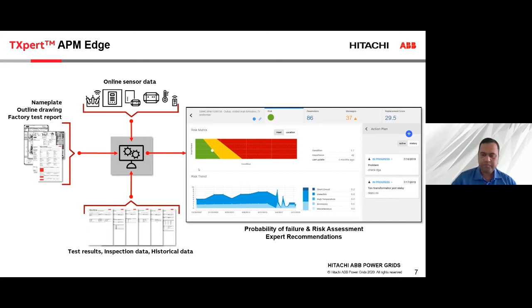As I mentioned before, we do a very nice fleet analysis, and on each transformer we do DGA analysis, both offline data and online data. We have the thermal model, standard oil test, bushings, tap changers. We use all of that data to calculate the probability of failure and what is the risk associated with operating that transformer at that particular condition.